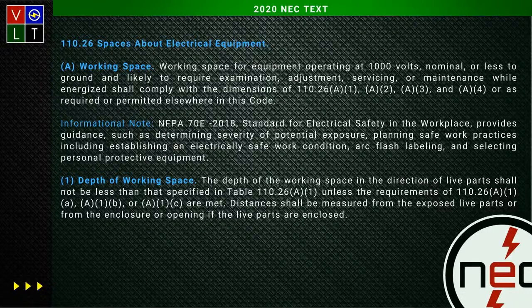I remember looking at the video he was making comments on, and the first thing I pointed out is, how can you even make an assumption what the arc flash boundary is? Because it was where you could rack in and out, and one of the other parts of the calculation, and also using the table, is the distance where the connection point is. This was further back in the equipment, so you got a bigger distance, which limits that distance. Of course it depends on how much pressure can build up inside that enclosure and push it out, but they'll give you a distance based on those three values to do your calculation in Annex D.